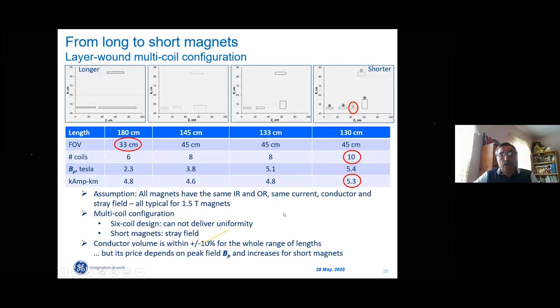Okay, now, let's talk about coil shape. Most magnets use what we call a layer-wound multi-coil configuration. Here I show how coil shape changes when we go from a longer magnet to a shorter magnet. We try to meet the same requirements, but make the magnet shorter and shorter and shorter. Initially we start with a six coil configuration, where two coils are shielding coils.